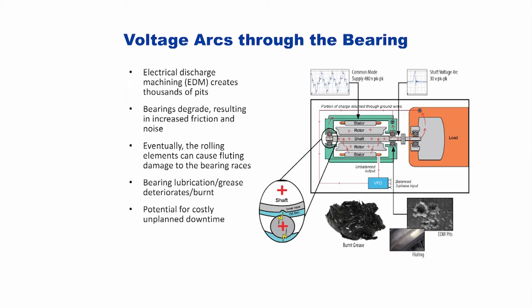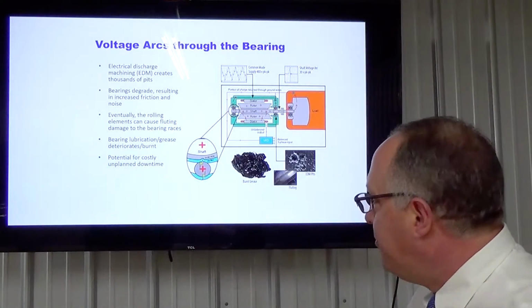These voltages actually arc through the bearing. Electrical discharge machining creates thousands of pits. The bearings degrade, resulting in increased friction and noise. Eventually, the rolling elements can cause fluting damage to the bearing races. That fluting will cause bumpy aspects in the race of the bearing itself. Lubrication grease can deteriorate and get burnt, and there's the potential for the unplanned downtime that we discussed. You can see here burnt grease, you can see the little pits, and you can see the fluting. We'll look at those a little bit closer.